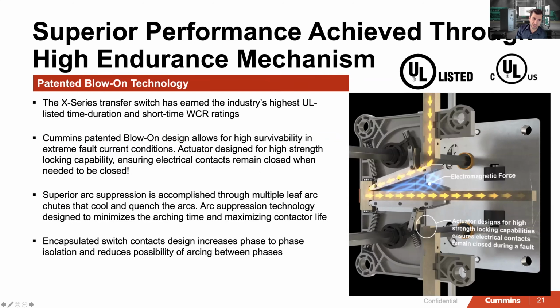The superior performance of the transfer switch: again, it's UL listed, and CSA and UL are harmonized. It has the highest WCR in the industry. It's the blow-on technology that's invented by Cummins. It uses the electromagnetic force to even help us keep the contacts closed during a fault. The superior arc suppression is accomplished through multiple arc leaves, arc chutes that cool and quench the arc. All the contacts of the transfer switch have been enclosed in covers to decrease the possible phase-to-phase arcing.